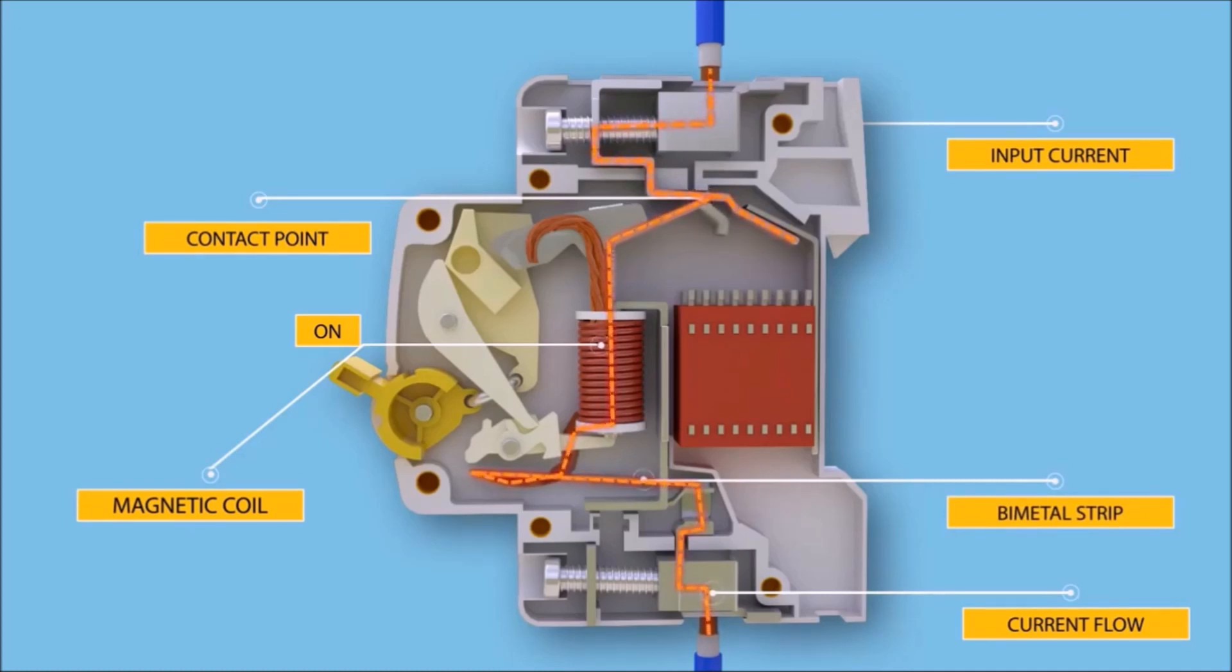Under overload conditions, the current through the bimetallic strip causes its temperature to rise. The heat generated within the bimetallic strip is enough to cause deflection due to thermal expansion of the metals. This deflection releases the trip latch and the contacts get separated.